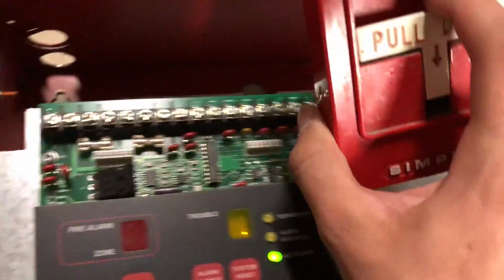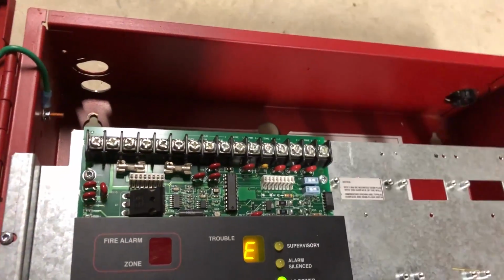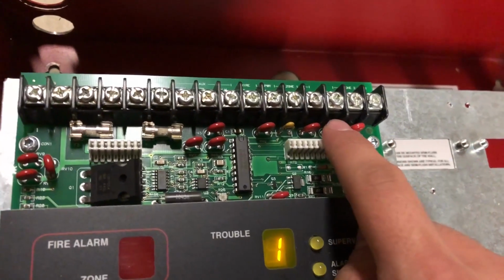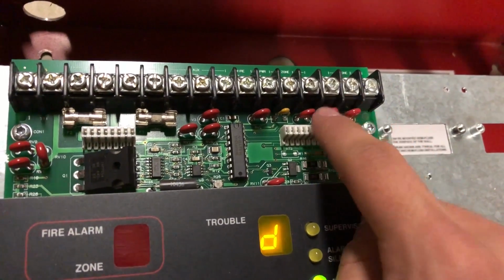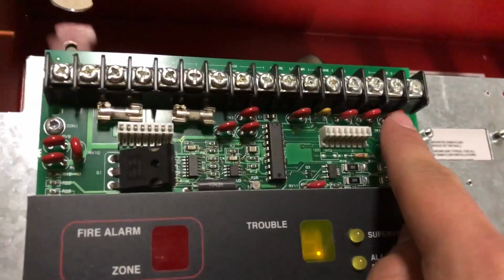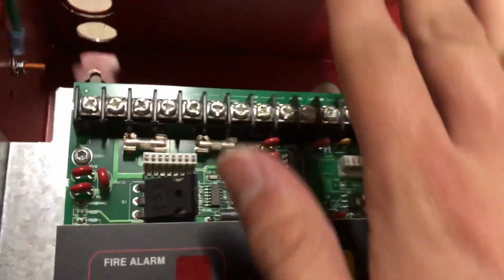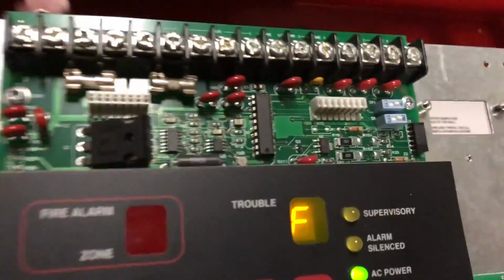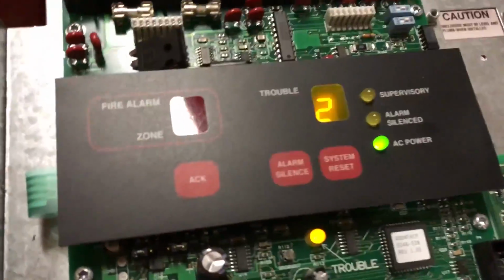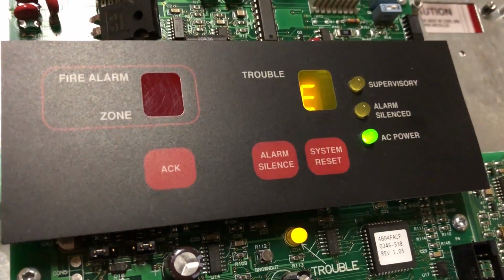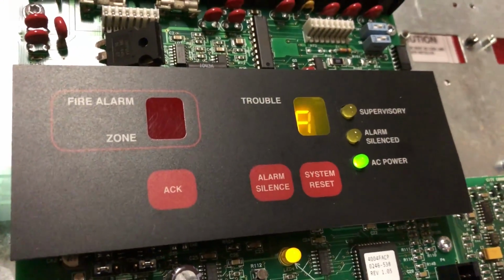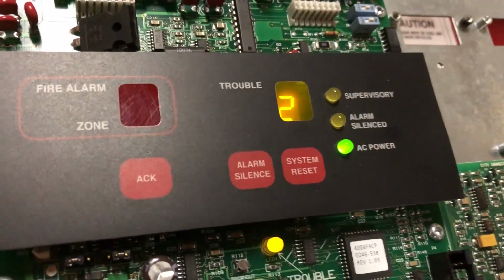They have to be in order for it to work properly. So what's going to happen is, when I, for example, pull a pull station, it will cause an increase in current up to whatever these, what I assume are resistors, limit it to on the board here. And when the panel sees that current shoot up, that's how it knows to go into an alarm. Furthermore, information upon that will be found in a video that I've already linked before in the panel build series. I can link that down in the description if you guys are interested.